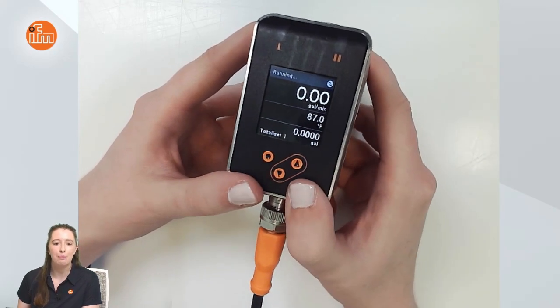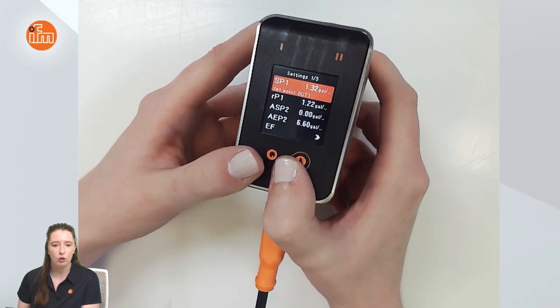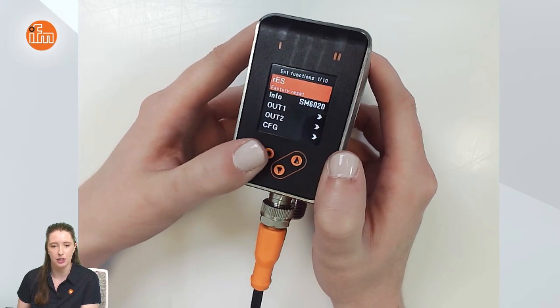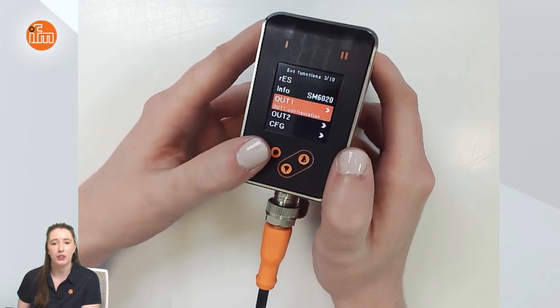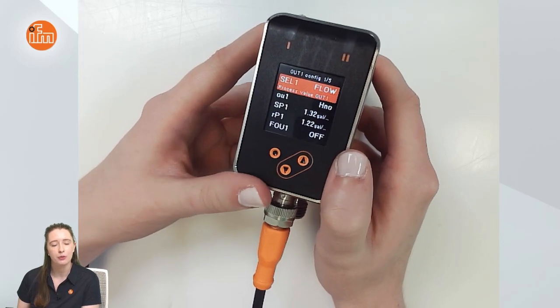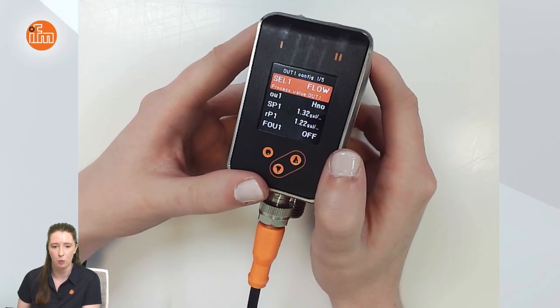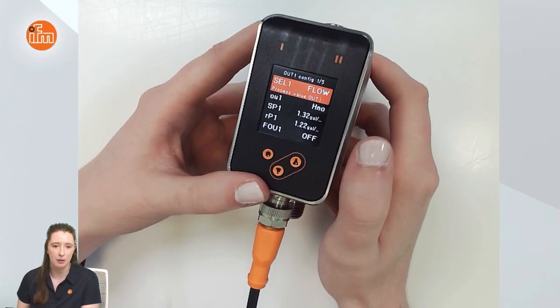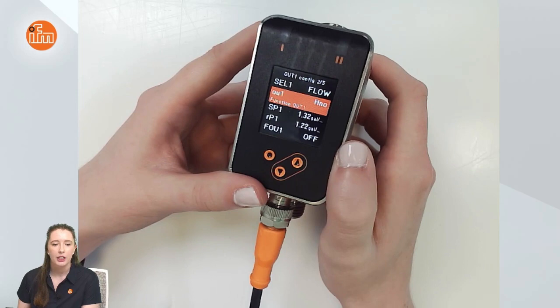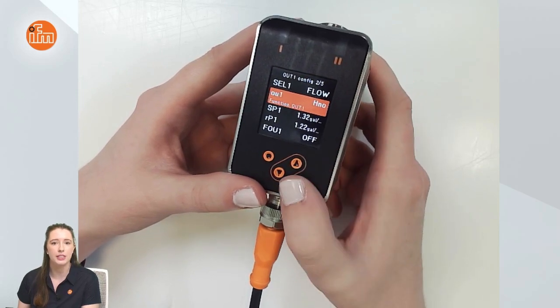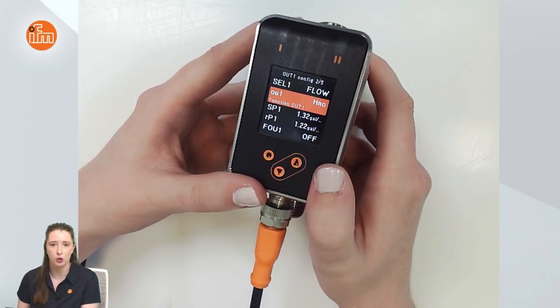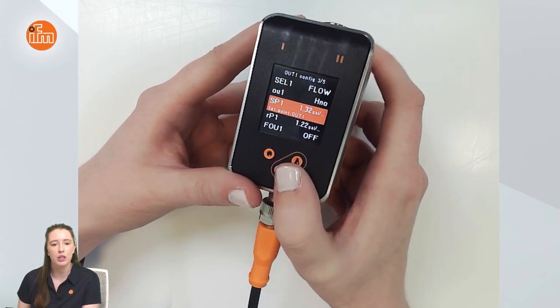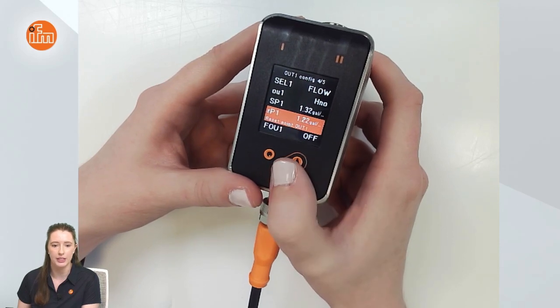Now let me take you back into the menu by pressing the enter button. We'll go back into the extended functions menu by going to EF and pressing enter. Going into the output 1 menu, you can see all of the parameters specific for output 1. Output 1 can be set to monitor either flow or temperature using the SEL1 parameter. Here you have OU1 where you can set it for your different switching outputs, which are defined on the Learn More page. And here you have your SP1 and RP1 parameters that you can go into and set.